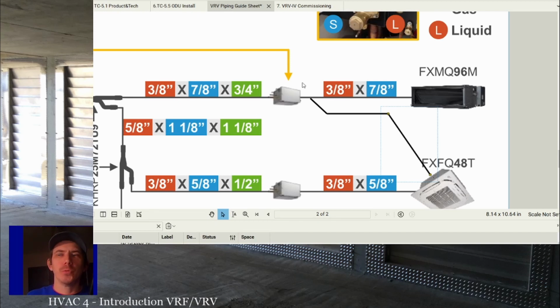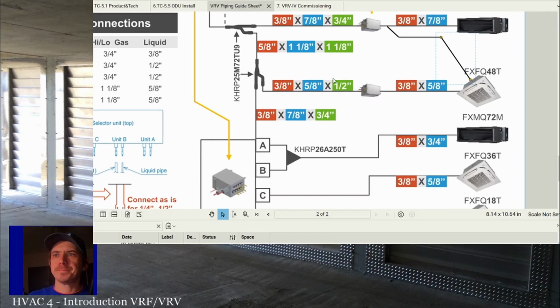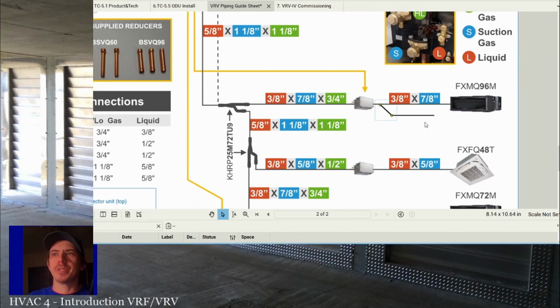So it's something to keep in mind. But you will see multiple units fed off of one branch selector, and generally that's a good thing. Basically every branch selector is one thermostat. Now, you can have separate thermostats off of one branch selector, but the other way to think about it is if these units couldn't be on the same thermostat, they shouldn't be on the same branch selector. Okay? So there's that diatribe.